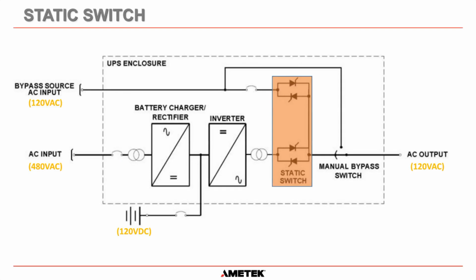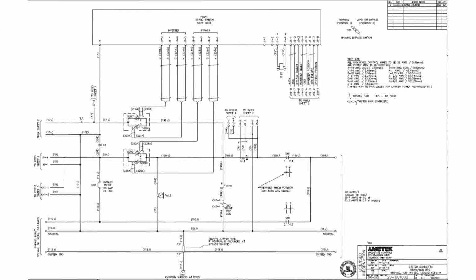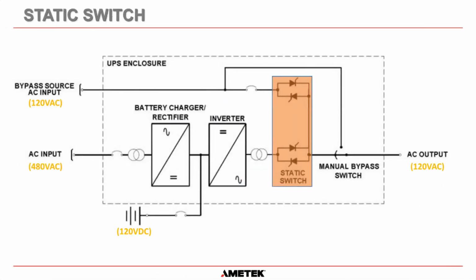And next we have our static switch. Now remember, static switch, static does not mean static electricity. Static means no moving parts. Static as in still. There are no moving parts. Okay. So you can see on this previous drawing, we have one static switch here and one static switch here. This is the inverter static switch, and this is the bypass static switch.